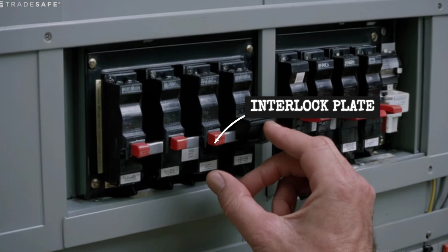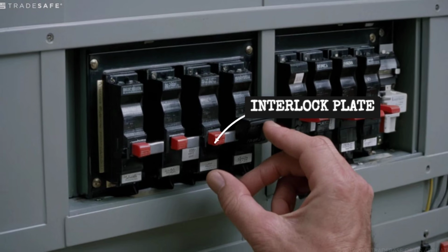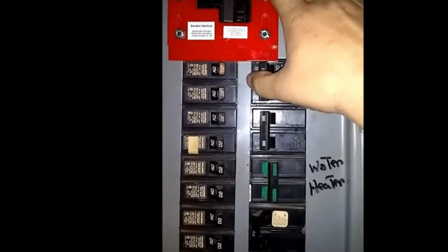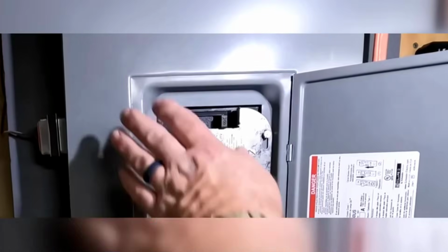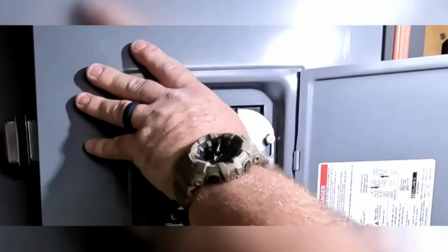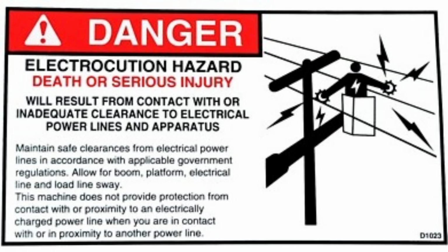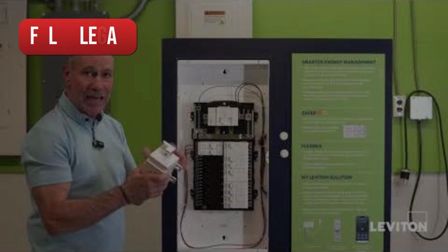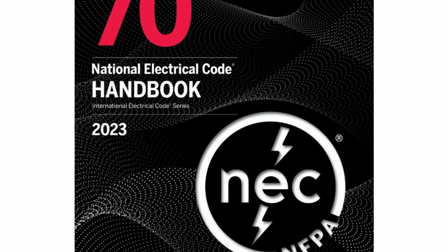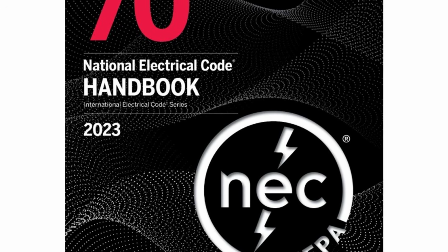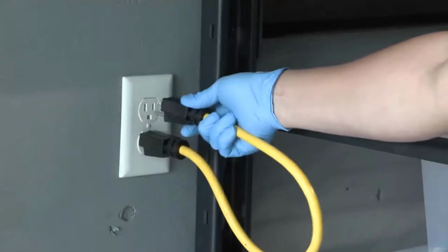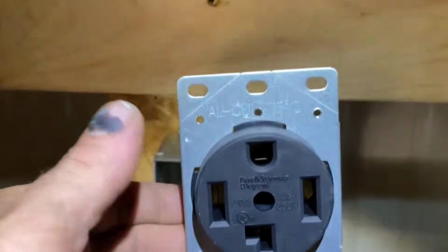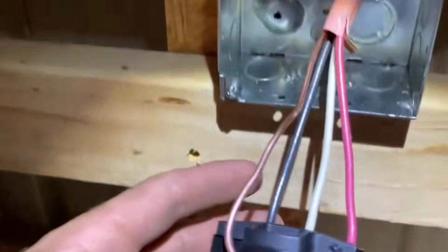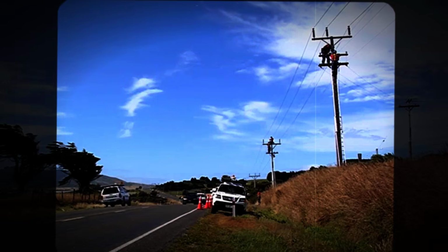This metal plate physically slides up and down on the face of your breaker box. It mechanically forces the main grid breaker to be turned off before the generator breaker can be turned on. It makes it physically impossible for the two power sources to mix. This setup is fully legal. It meets the National Electrical Code requirements. Most importantly, it completely prevents the dangerous and highly illegal practice of using a suicide cord to backfeed electricity into your dryer outlet, which can kill a lineman working on the street.